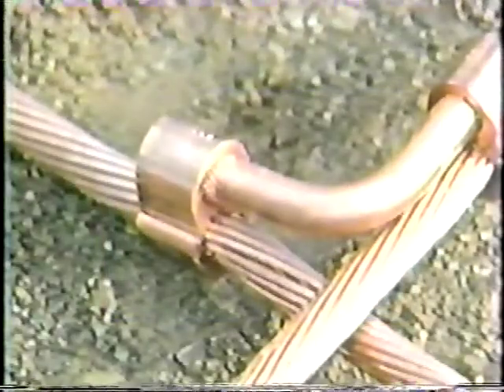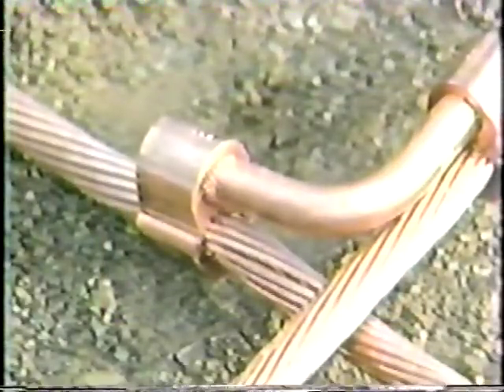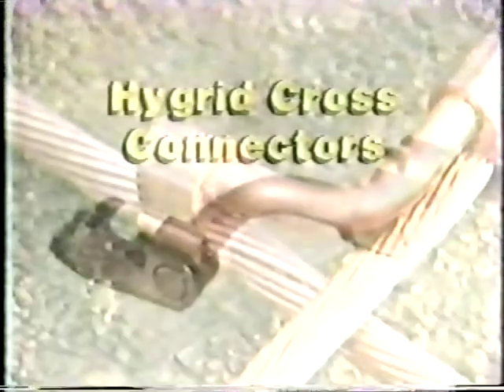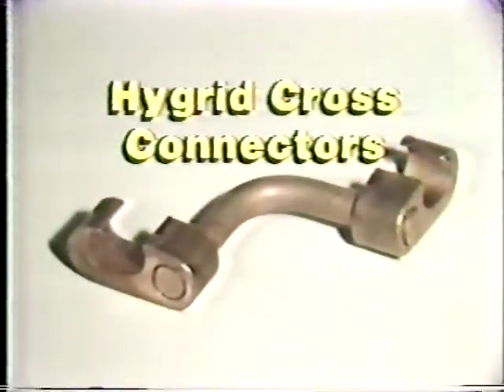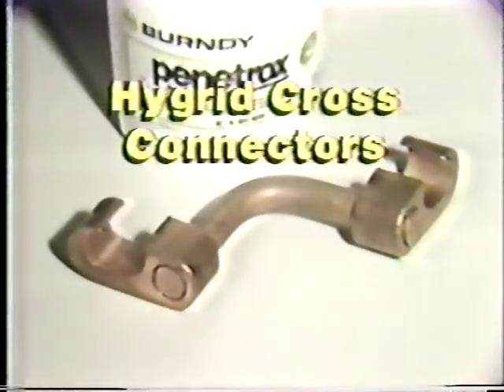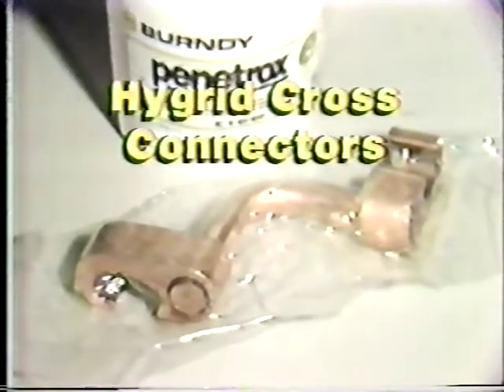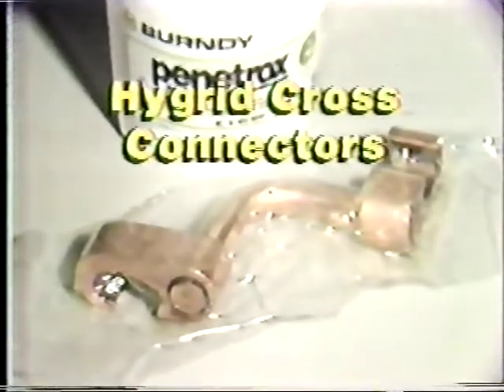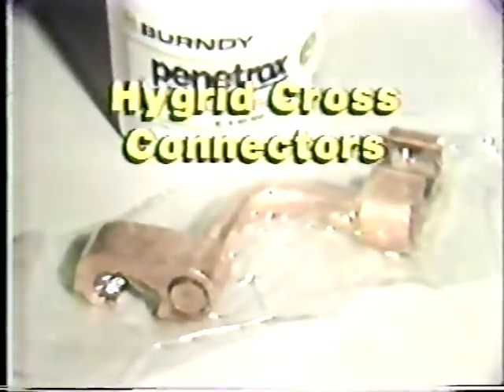Burndy builds Hygrid Cross Connectors to provide faster dissipation of fault currents. These connectors are made of high conductivity electrolytic copper and are pre-filled with Burndy's unique Penetrox E oxide inhibiting compound, then strip sealed to prevent contamination. Because they're UL listed and meet the latest requirements of IEEE 837, these connectors are ideal for direct burial applications.